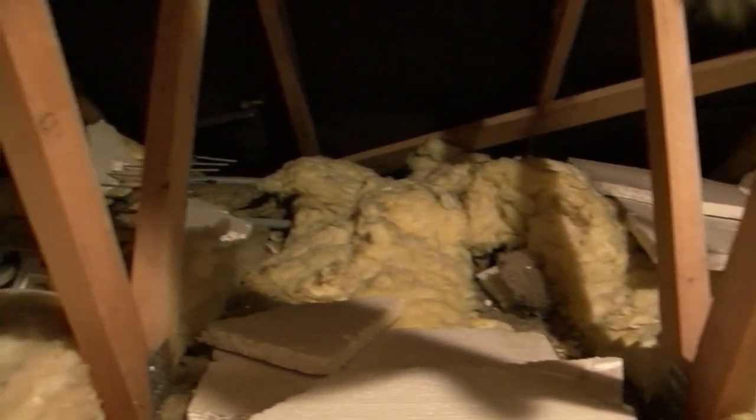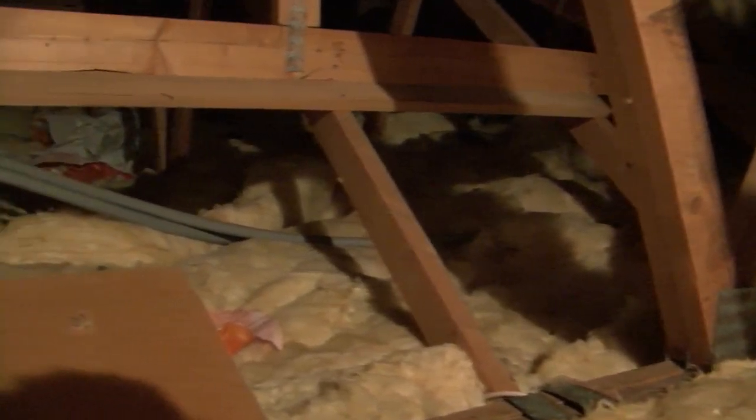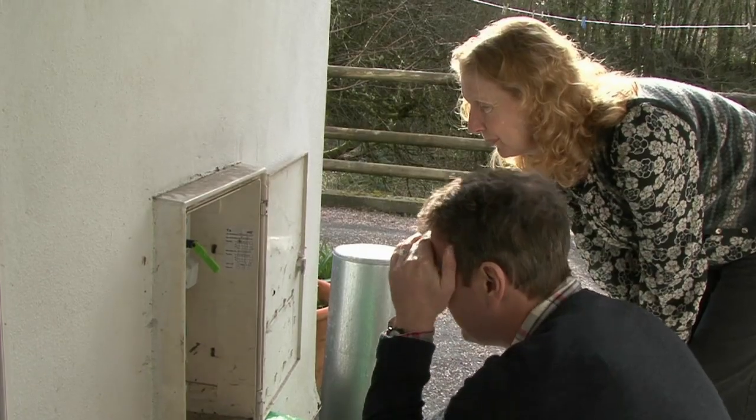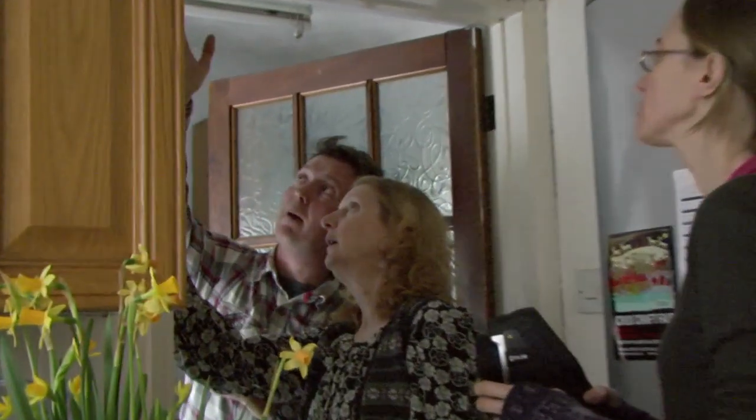There's a hundred mil of insulation but it's been put down over some older insulation, and there are loads of gaps. That's coming through the fabric of the building — straight outside, or finding its way through, or from up in the loft as well. What you want to do is seal that literally with some silicone, and then that will stop air infiltration through into this. All of this is about making sure your boiler doesn't have to work as hard.